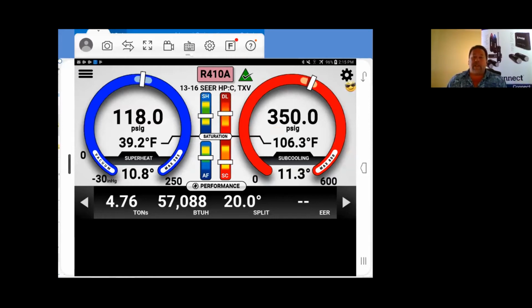So this is just demonstration information, but that's how fast everything gets pulled up. You have all your information set, you've got your target set, your saturation temperatures on both the low side and the high side, your superheat and subcooling, and then scrolling across, there's your targets.